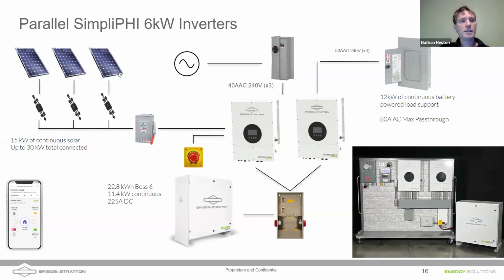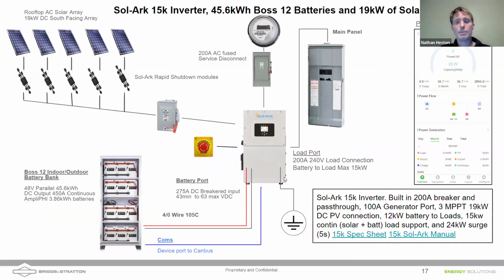What I'm showing you here is DC coupled solar. These are rapid shutdown devices, which are required on rooftop solar. A disconnect here, 2 inverters that are paralleled. I'm showing a Boss 6 cabinet here, which gives about 23 kilowatt hours of storage, with DC breakers here that are required for our inverter. The Sol-Ark has those DC breakers built into it. It has 2 200 amp breakers in it, and I'll explain why in a little bit.